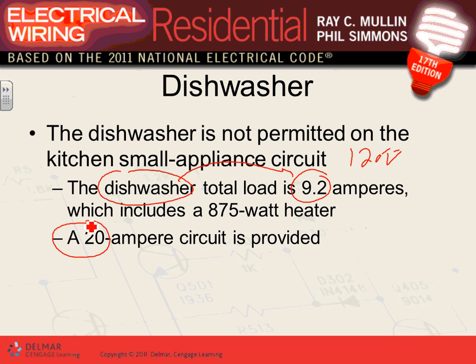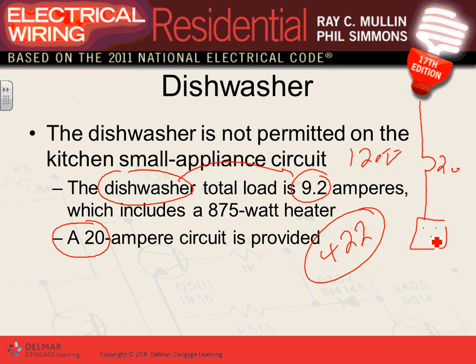They're appliances. Do you guys remember Article 422 from yesterday? We said if the amps of the appliance are 13.3 or less, you have to provide the appliance with a dedicated 20 amp circuit. So that's based on this concept. We provide the same thing for the garbage disposal. We provide a dedicated circuit. So what did we do? We provided a dedicated circuit, 20 amp, to a receptacle. And then here's my dishwasher, and we plug my dishwasher into this receptacle. Now, a couple of things you need to know. I have my branch circuits right here.